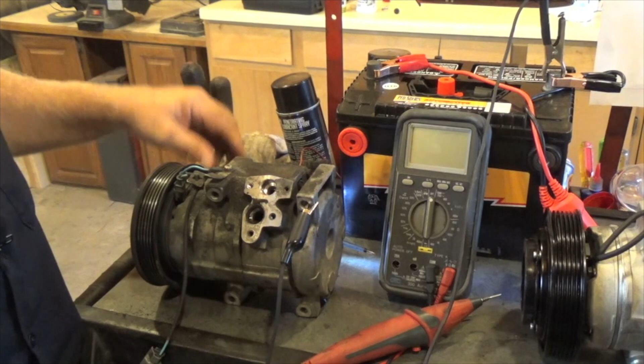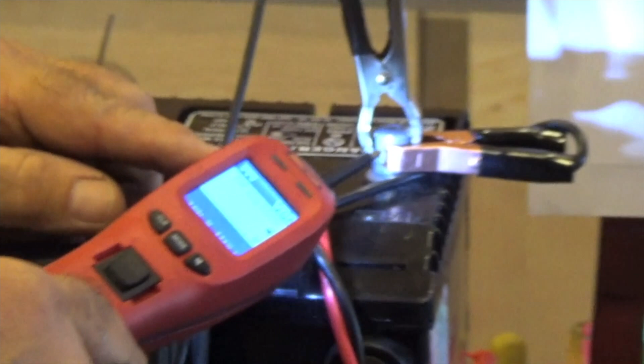Now, with the power probe you can tell which side of the battery you're on, because if I touch the positive, I have a red light and it shows the voltage, and if I touch the negative, I've got a green light and the ground. So with this being connected to the case, I should be able to touch this to the case of the compressor and see that we're on ground.